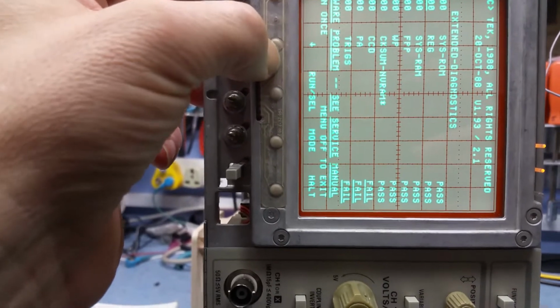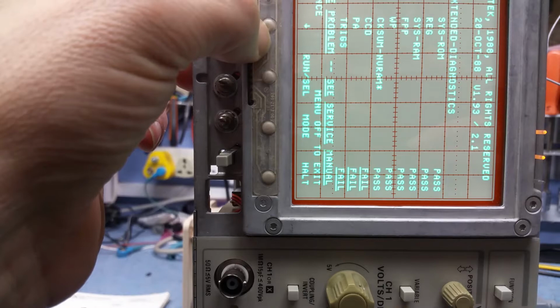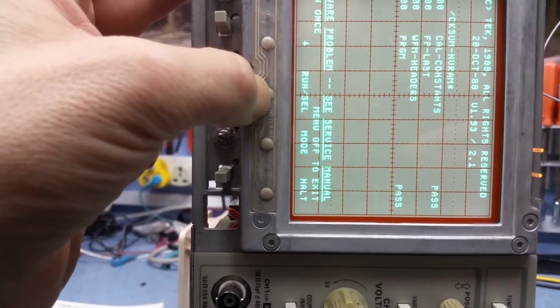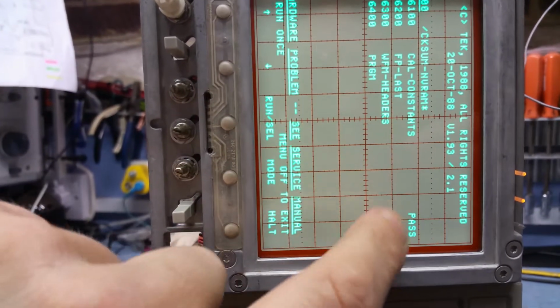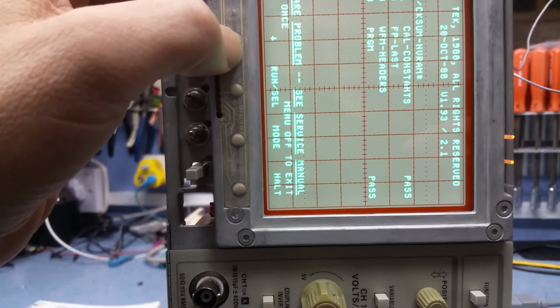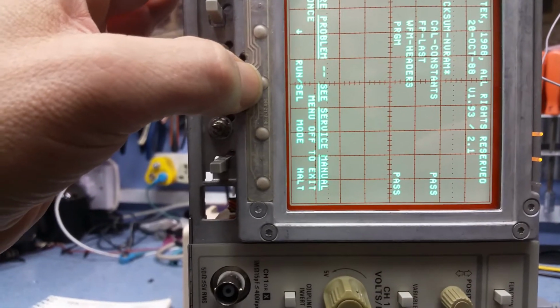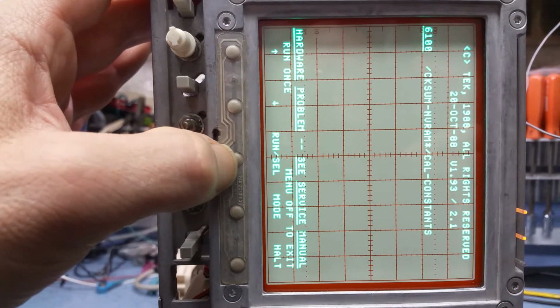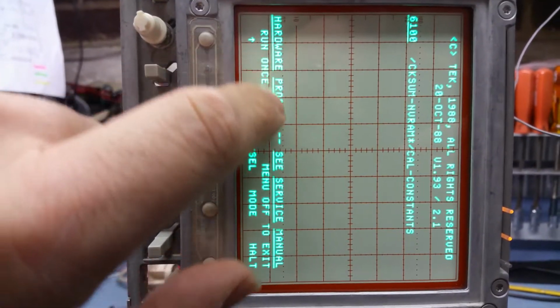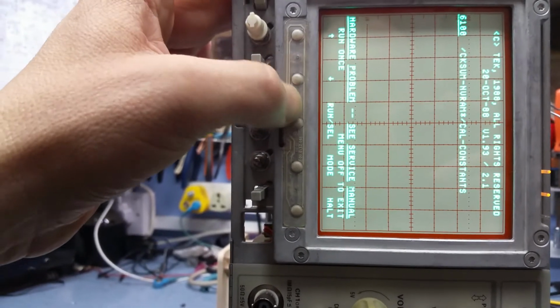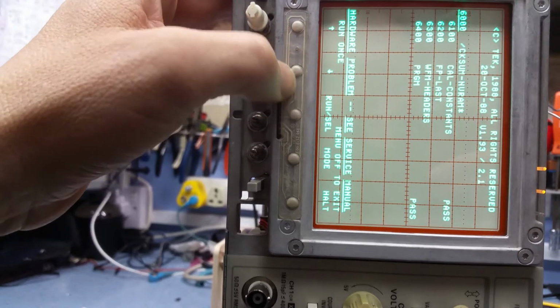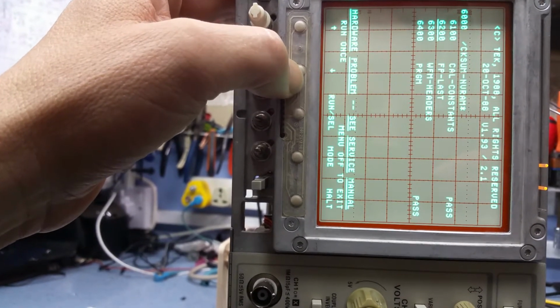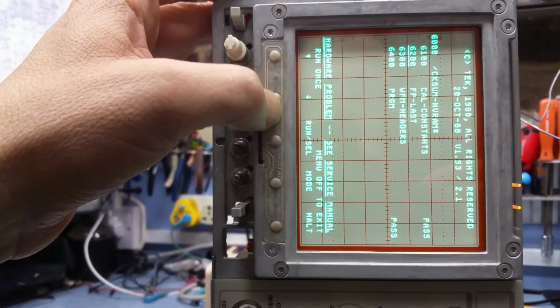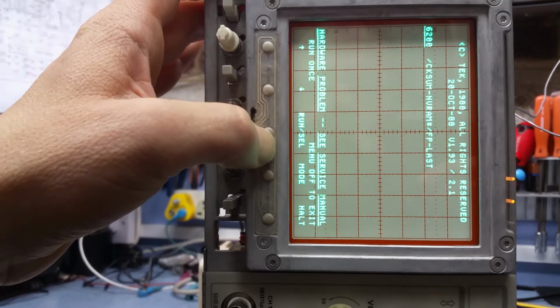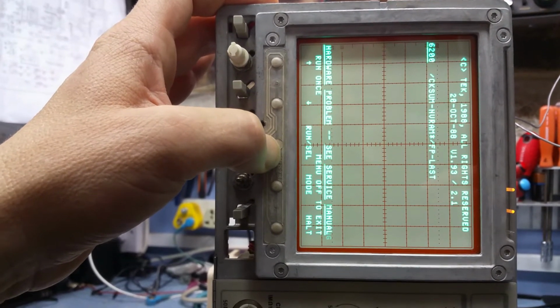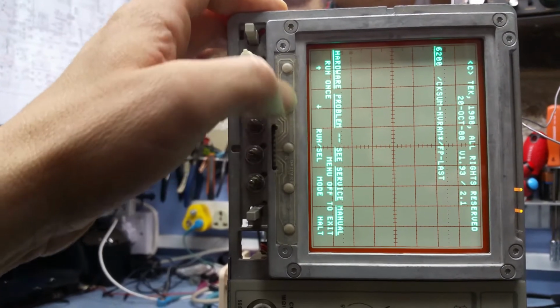So let me just scroll down. I've got the front panel off, so it's not so easy to use. And then we go run select. Now if you look here, it's passed on these two things, but not on the other two. So if you scroll down, I'll run a self-test on this calibration constant. So as soon as I press this, watch what happens. It comes up with hardware failure, see manual. So okay, we go back. So we try another one. Let's try this FP last. I assume that's floating point. Let's run that selected one. And we'll execute that. Same thing, hardware problem, see service manual. Okay, so we go back.